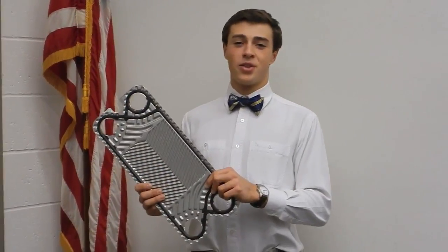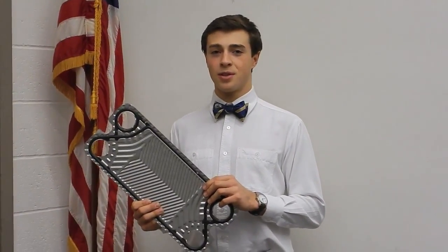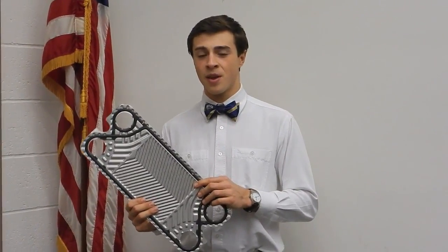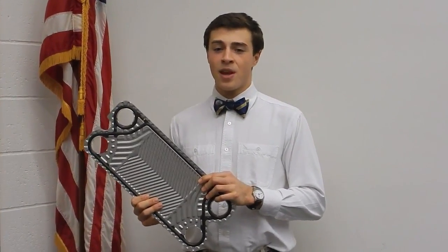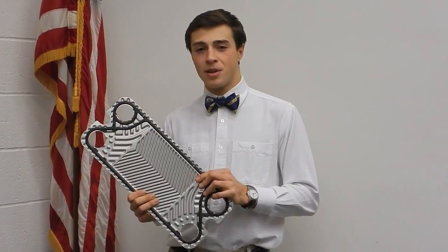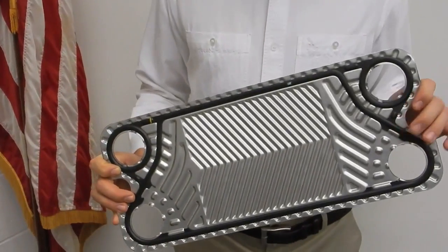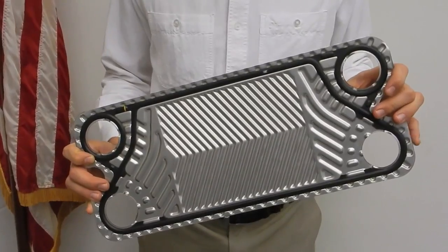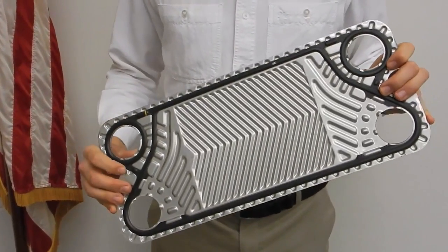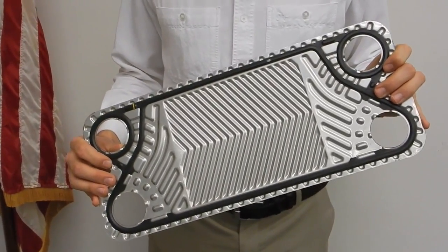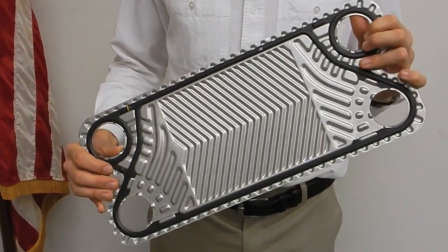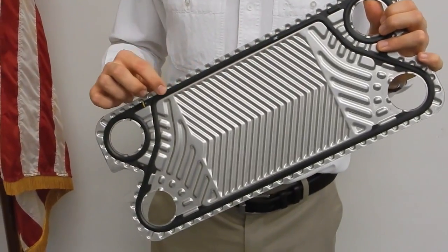In a plate-type heat exchanger, corrugated plates like this one are used as the barrier between hot and cold fluids. The corrugation serves to increase the area of heat transfer, create a turbulent flow, and allows the material to be thinner because it strengthens the plate. The use of advanced materials like titanium can make the plate stronger and more durable. This allows plates to be made thinner, increasing heat transfer. Rubber gaskets around the outside of the plates seal them against one another.